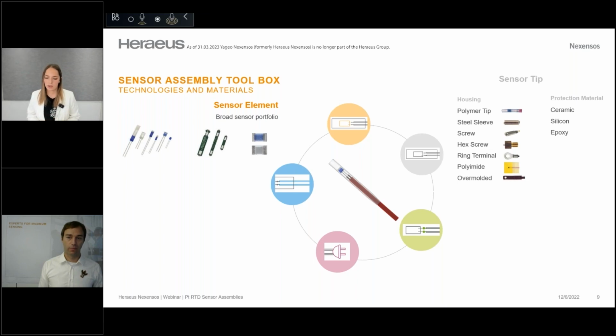When a customer is asking for an easy installation of the sensor, maybe he wants to screw it in, then a screw, a hex screw, or a ring terminal could be a good solution for the customer. And the last example to give: the Polyimide and the overmolded sensor housing are suitable for surface measurements. And sometimes you will need a protection material inside that housing to fix the sensor and also to ensure a good response time. Here again, just some examples: the ceramic, the silicon, and an epoxy.